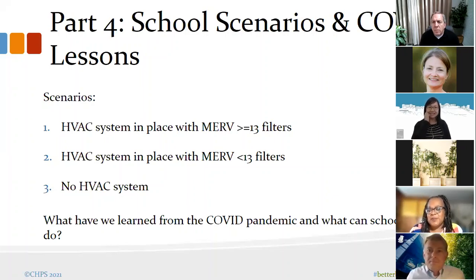And for the last case, eventually we would like to bring some ventilation to these classrooms. So for the longer term and for COVID, I agree, filtration really works. I think for the longer term, we'll need to think about what our game plan is in 5-10 years from now. There are retrofit solutions for classrooms. I'm from the Bay Area in California, where the temperature is pretty moderate, so an ERV, a fitted ERV, would serve that purpose. It's a few thousand dollars kind of solution, but it brings in outside air. Our winters are not too cold, summers not too hot, so maybe it's an easy one.